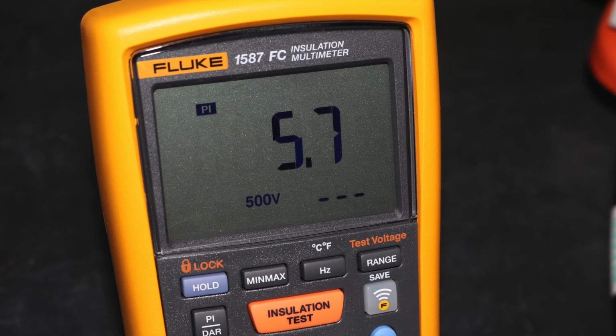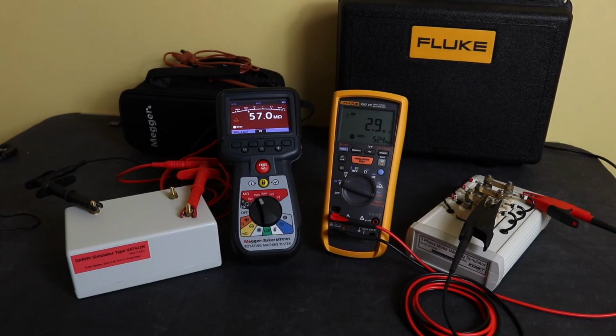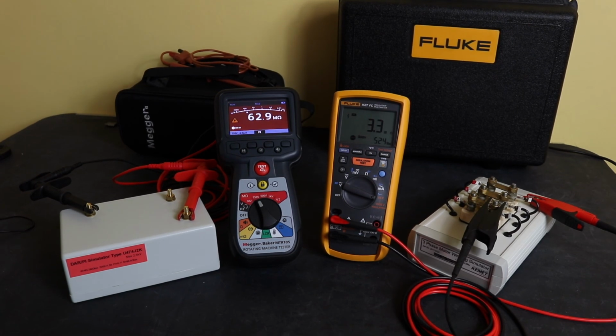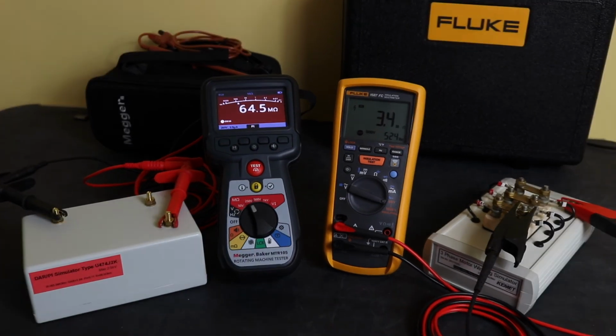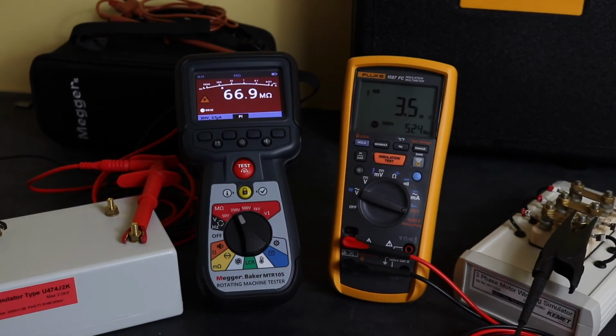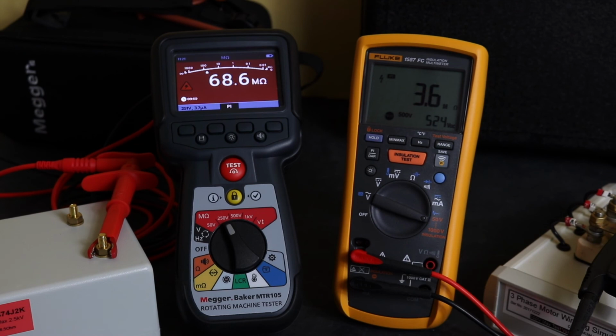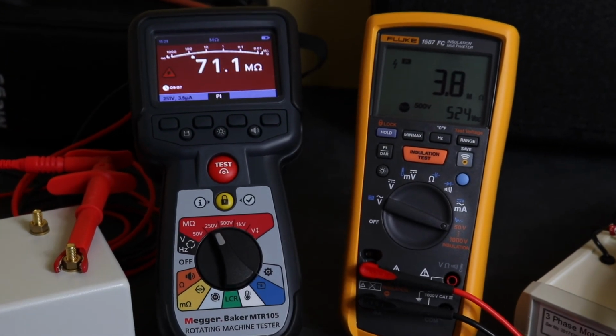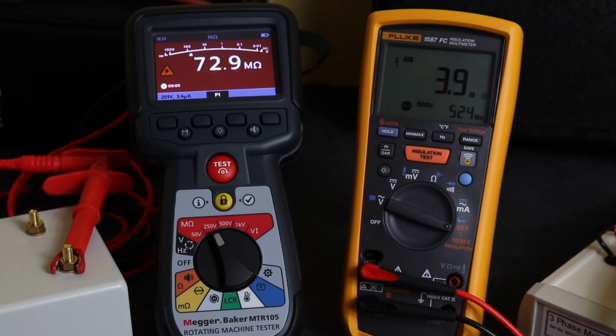The other difference as well is that during the test, the MTR105 will actually display a time clock as well as the current if you want that, so you can record readings manually as you go along with tests. With the 1587, you don't actually get a time clock with it. So if you haven't got an iPhone or an iPad to record the results, you actually need a separate timer with this to be able to record interim data to get your resistance curve.